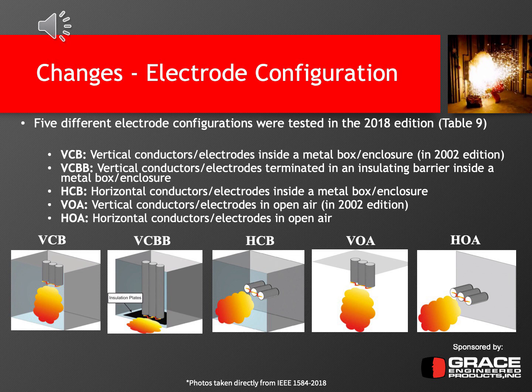VCBB is vertical conductors, electrodes terminated in an insulating barrier inside a metal box or enclosure, which is new. HCB, which is also new, is horizontal conductors, electrodes inside a metal box or an enclosure. VOA, which was included in 2002, is vertical conductors in open air. And then HOA, which is new, is the same as VOA, but with horizontal conductors in open air.